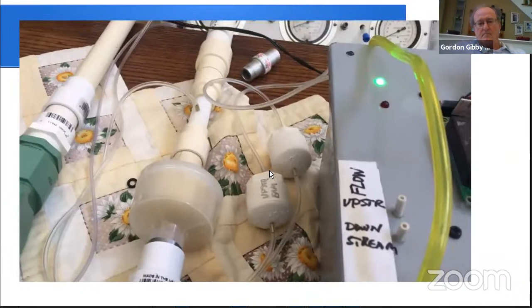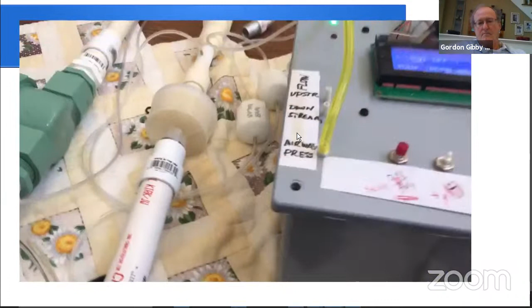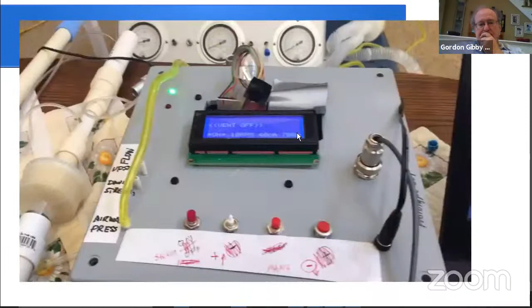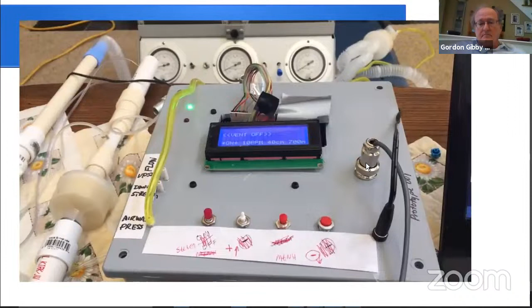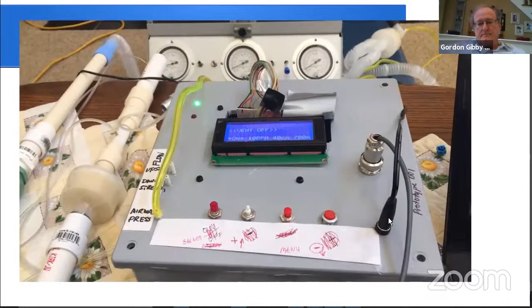Those two little cylinders are actually pneumatic low-pass filters. They're just a plenum. And then the signal from those goes into a differential pressure measurement system on the inside. This is one of my prototypes. We had to meet a whole bunch of FDA requirements. One of them is we can't have exposed conductors, so we used a CB microphone jack. The outside is not connected to anything. We power the system with a medical grade power supply.